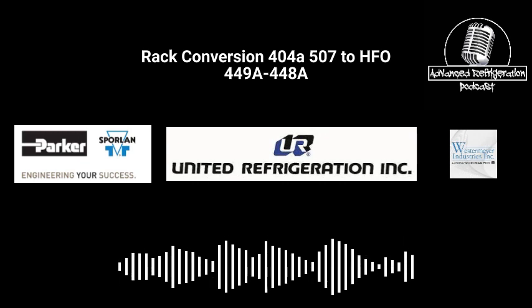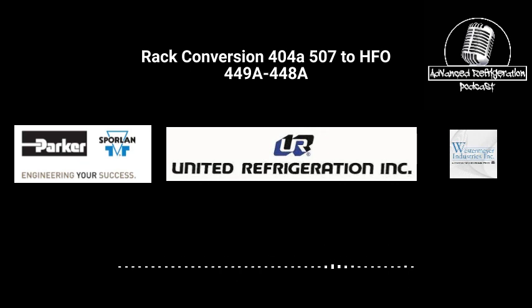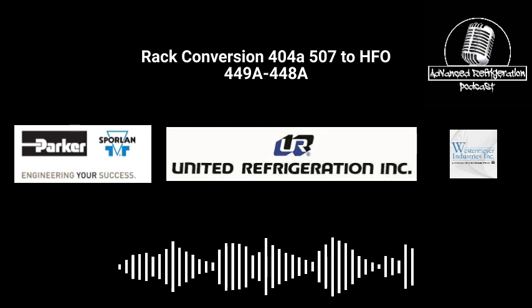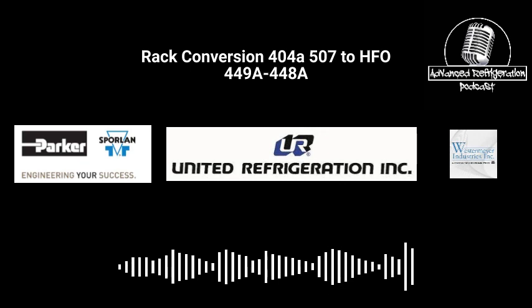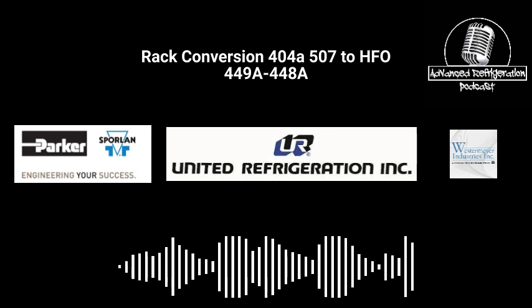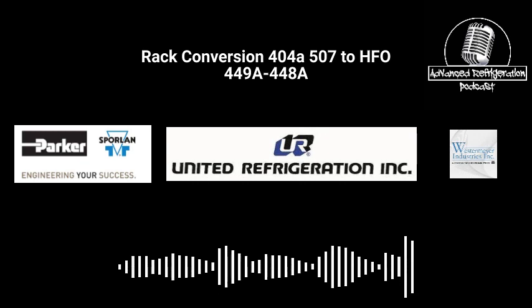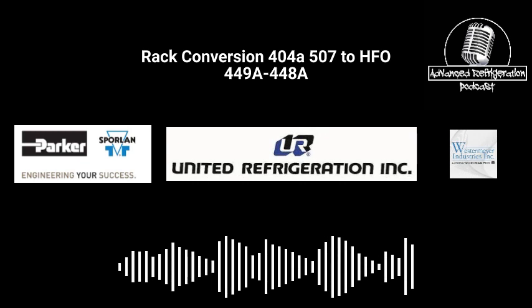Go ahead, continue. Sorry. So getting the power heads done is key. I've been a part of having to set superheats afterwards, and it sucks having the 404 power heads on there. It hunts all over the place. It doesn't maintain superheat well. Lots of flood back, lots of problems. So you're going to want to avoid that. So doing the power heads.